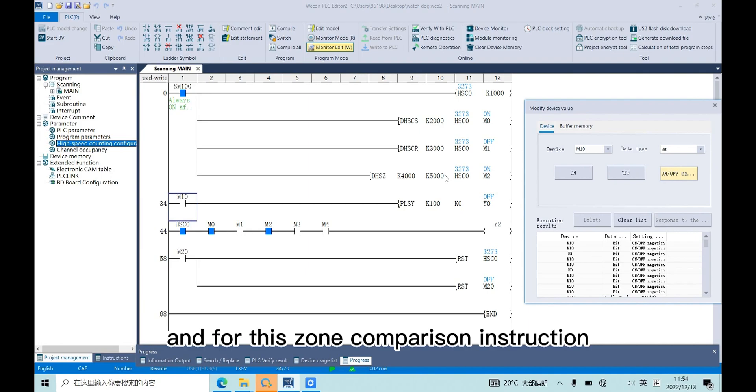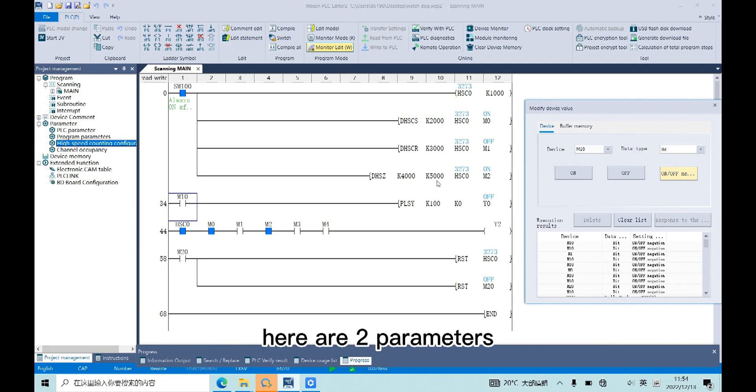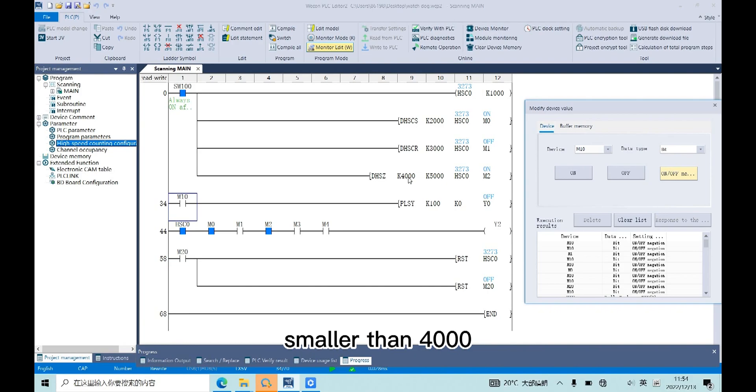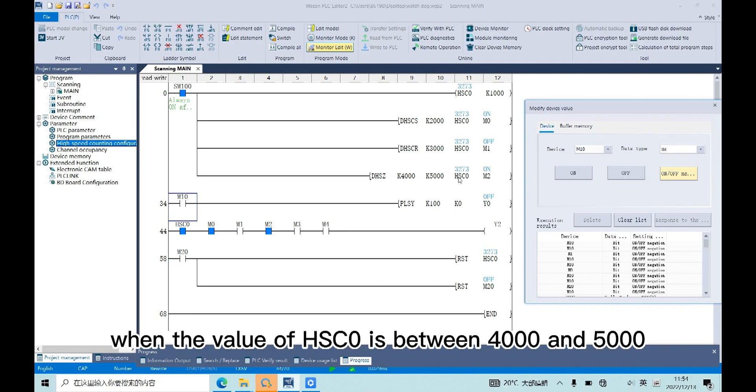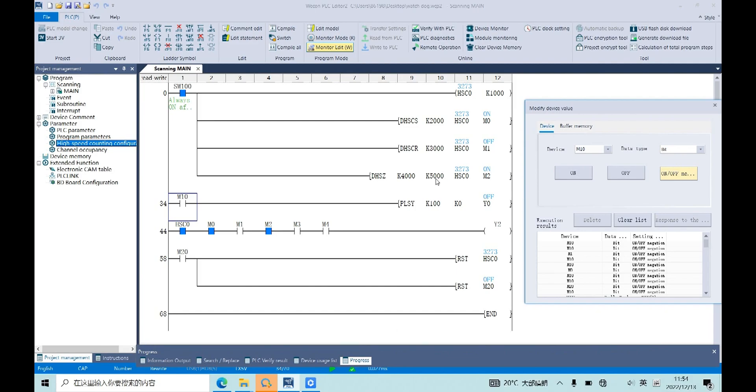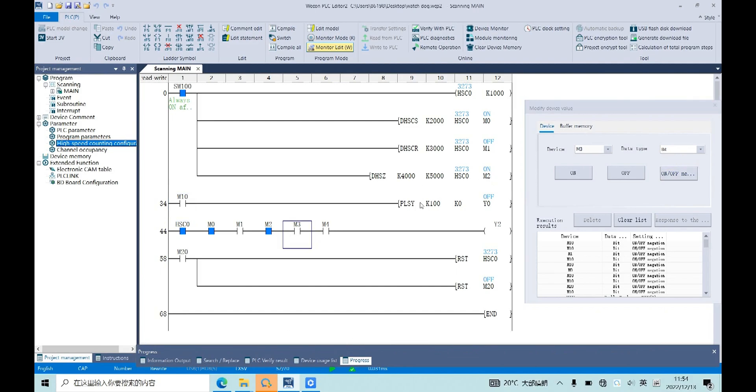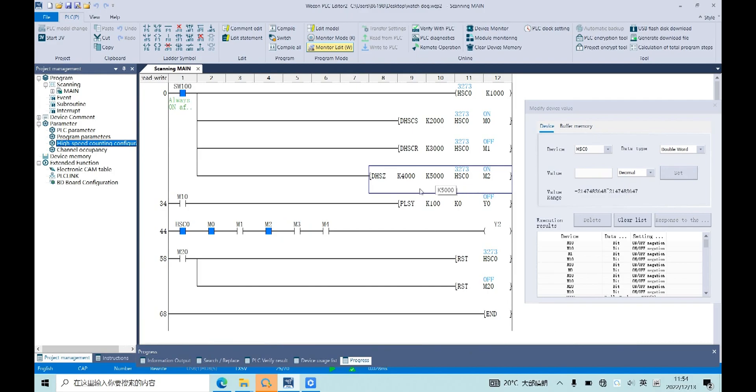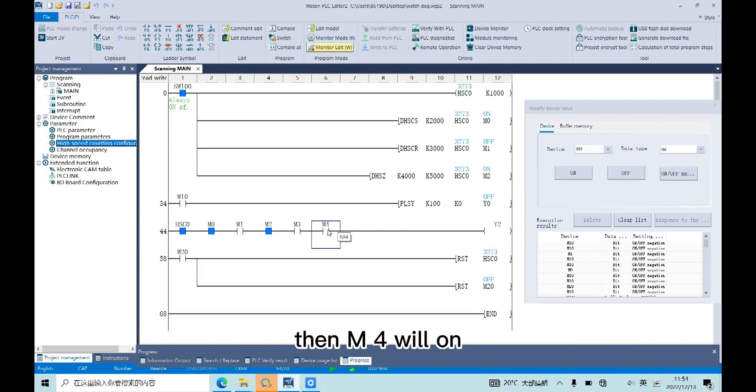And for the zone comparison instruction, there are two parameters. When the value of HSC0 is smaller than 4000, M2 will be on. When the value of HSC0 is bigger than 5000, then M4 will be on.